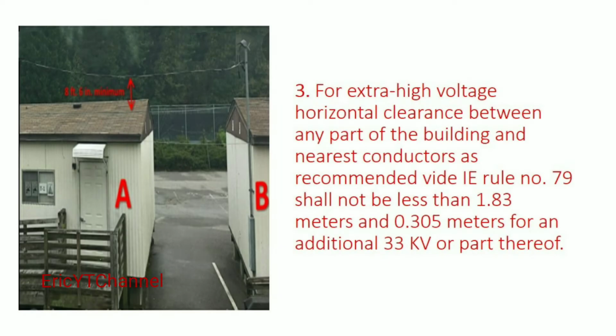Number 3. For extra high voltage, horizontal clearance between any part of the building and the nearest conductors, as recommended by IE Rule number 79, shall not be less than 1.83 meters, plus 0.305 meters for every additional 33 kV or part thereof.